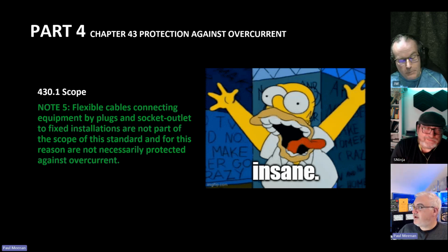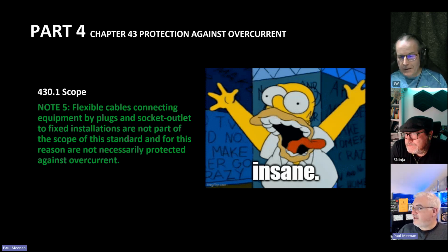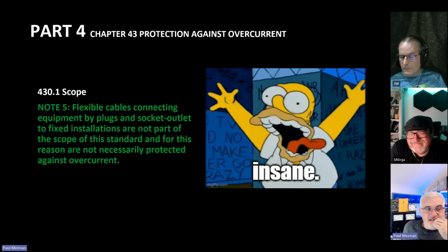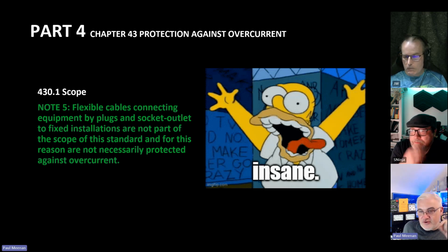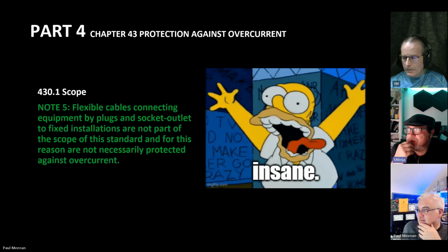So just for everyone, 430.1 is the introduction of the chapter that provides requirements for the protection of live conductors against effects of overcurrent. Now this, to me, Dave, I want you to ratify this or tell me to shut up. This to me says that potentially you could have a plug and socket that isn't fused, because you're then relying on the fixed wiring overcurrent protective provision. That's what that says to me. Flexible cables connecting equipment to plugs and sockets to fixed installations are not part of the scope.